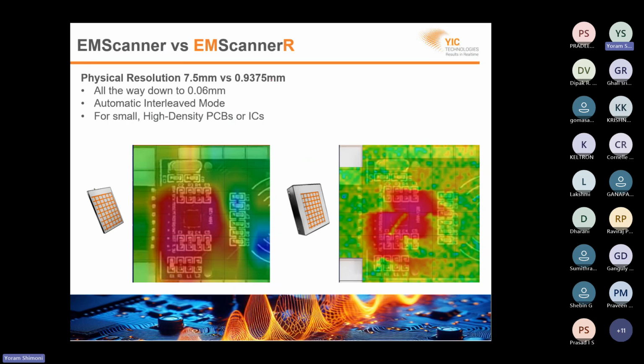Here you can see a 7.5 millimeter scan versus about a 0.9375 millimeter scan. So we can definitely see that emission is coming out from that component. But if you want to see details, including internal structure, now you need the high resolution. Again, it depends on needs. There's no really good and bad. It depends if your DUT is small or if the user is interested in the very fine details of the scan.